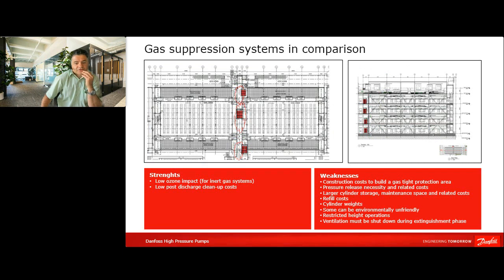I mentioned in the beginning that one of the conventional extinguishing systems for a data center is a gas suppression system. I just want to go through that system, that technology, and later on the sprinkler. For sure, a gas suppression system has clear advantages. It is a well-known system, used for years, has a low ozone impact or lower greenhouse effect, and the cleanup costs and post-discharge efforts are relatively small.